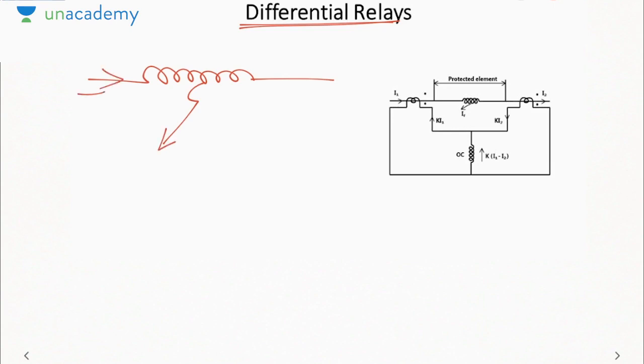Now suppose a fault occurs. If I is the current here and IF is the current going here, then the current will be I minus IF. If you compare the current at the two ends of the coil, both currents are different, and if there is a difference in the two currents, some current is flowing into the ground. If that is happening, there is a fault in the middle of the coil, or an internal fault in the coil. Internal fault means a fault which is inside the coil, between the two ends of the coil.